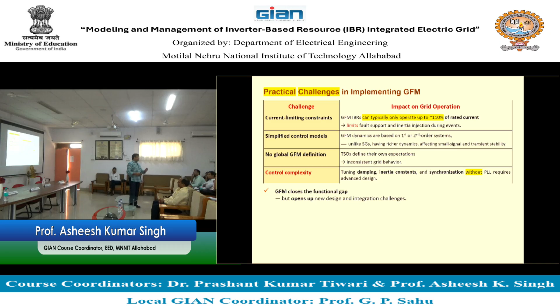The design level control complexities in grid forming IBRs are GFM behavior at the same points, just you will find one or two new points in that. This GFM behavior is controlled or software defined. Parameters like inertia and damping are not physical but must be designed and tuned, meaning emulated. No use of PLL, phase lock loop, is there in GFM, it was there in GFL. GFM must self synchronize as a voltage source. So that is also a challenge with GFM.